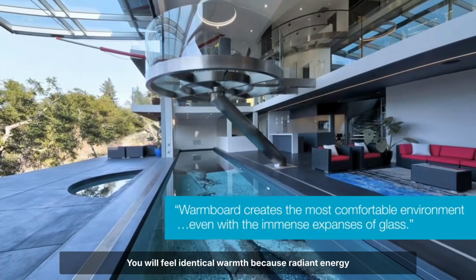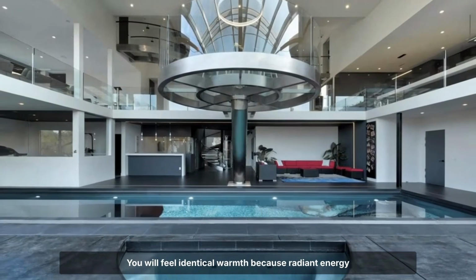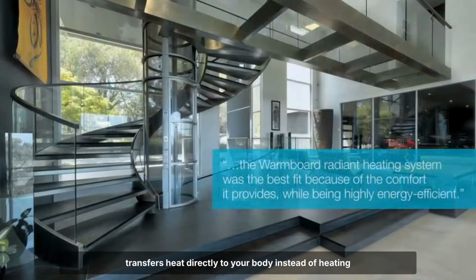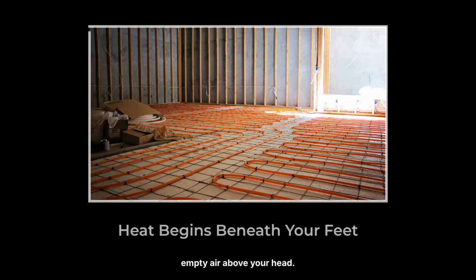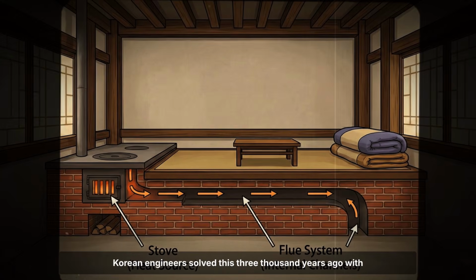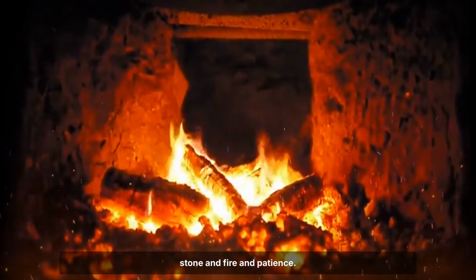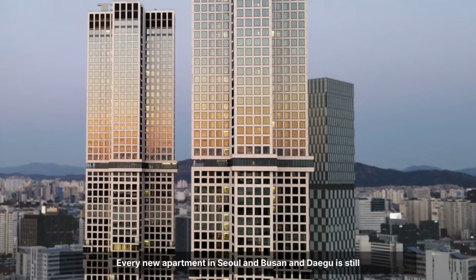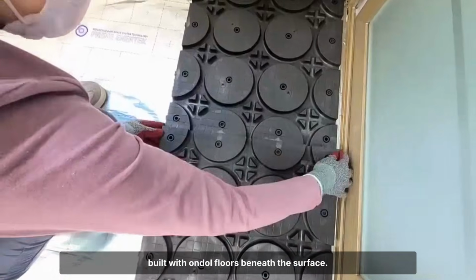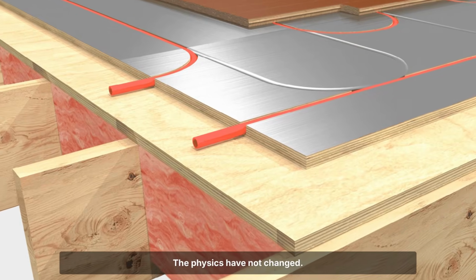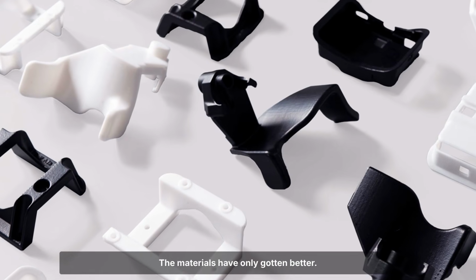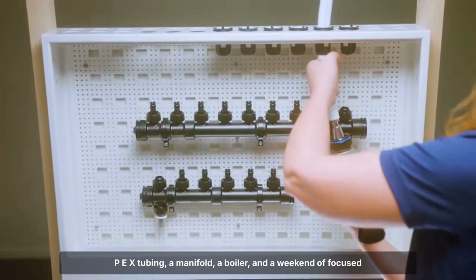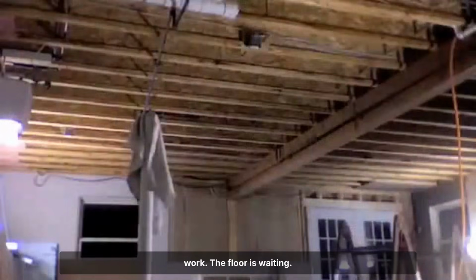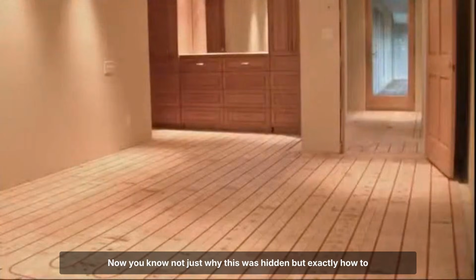Set your thermostat 2 to 3 degrees lower than forced air. You will feel identical warmth because radiant energy transfers heat directly to your body instead of heating empty air above your head. Korean engineers solved this 3,000 years ago with stone and fire and patience. Every new apartment in Seoul and Busan and Daegu is still built with Ondol floors beneath the surface. The physics have not changed. The materials have only gotten better. PEX tubing, a manifold, a boiler, and a weekend of focused work. The floor is waiting. Now you know not just why this was hidden, but exactly how to build it yourself.